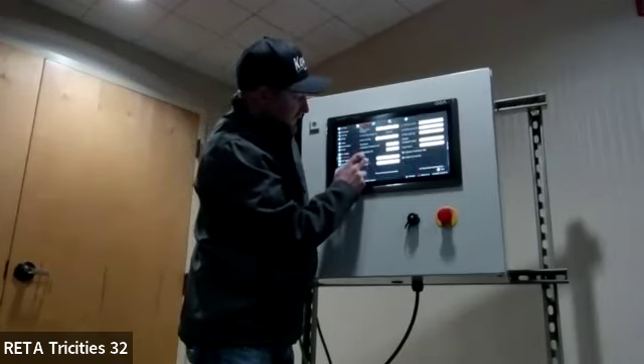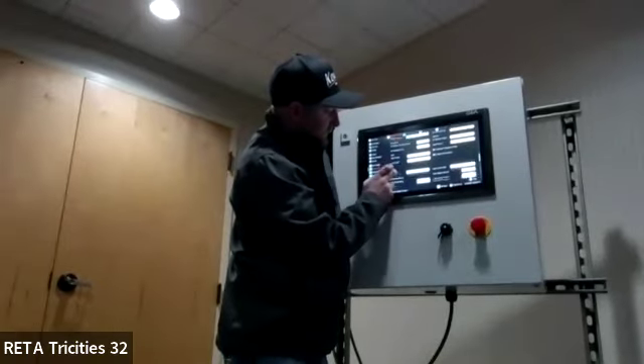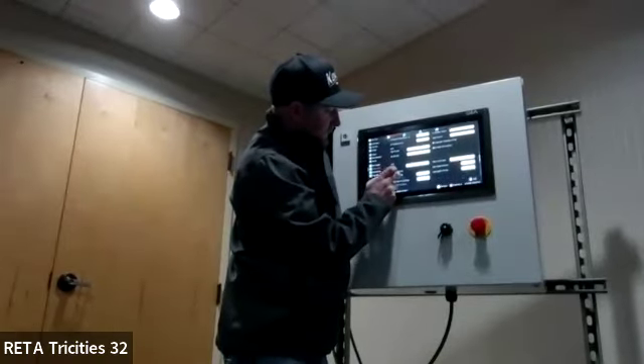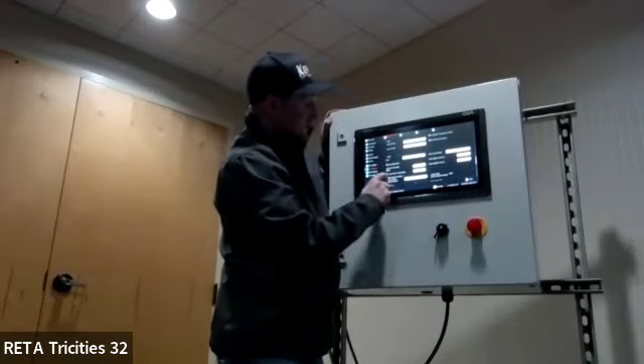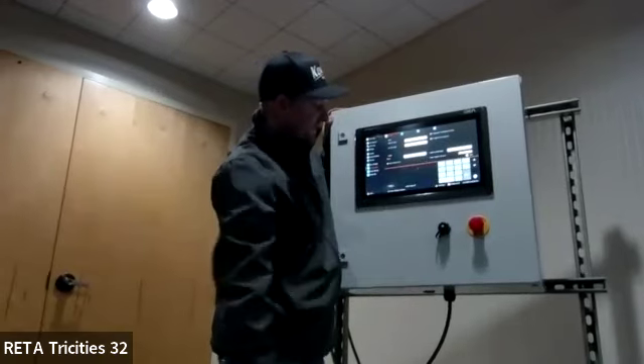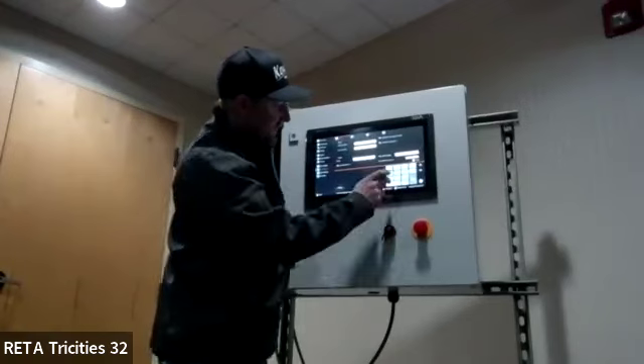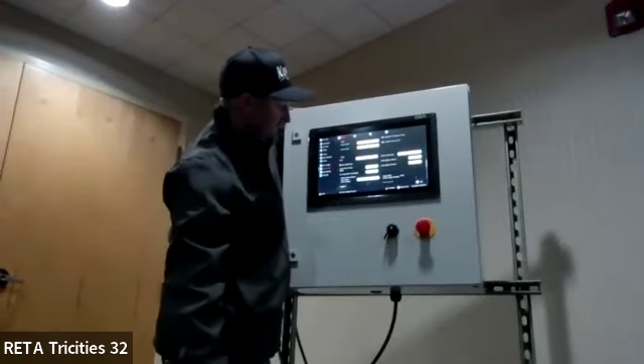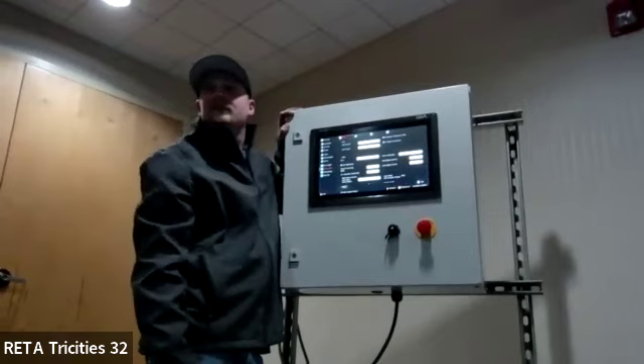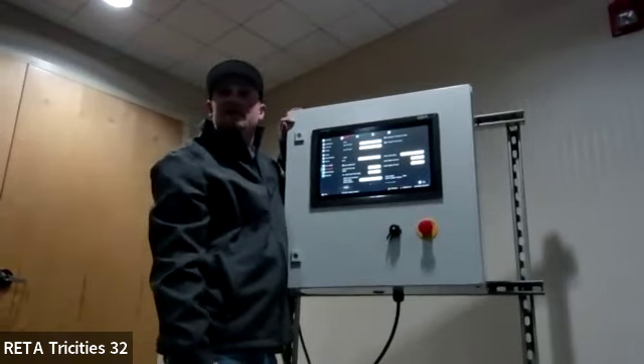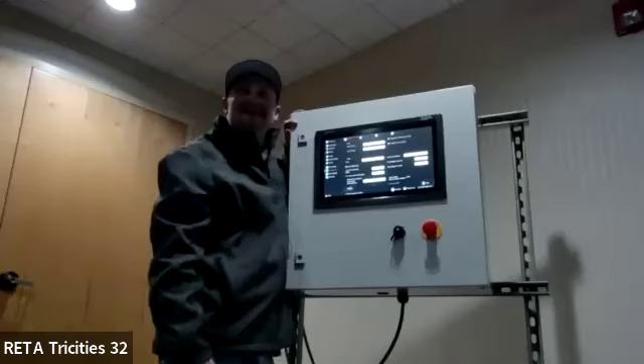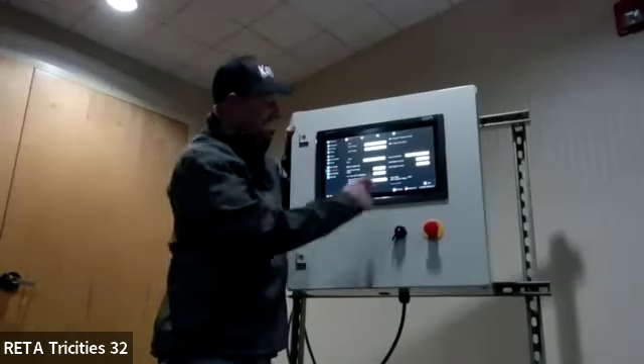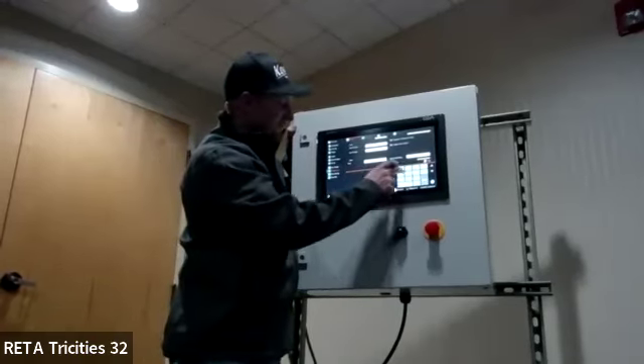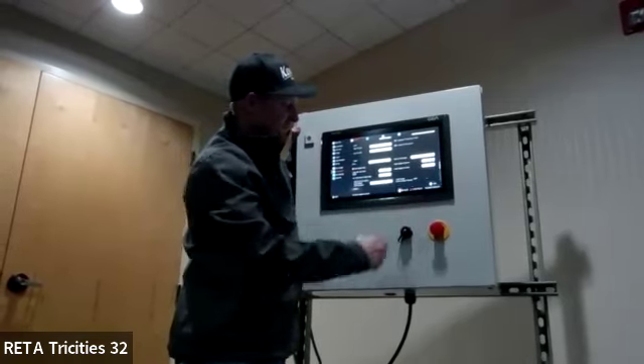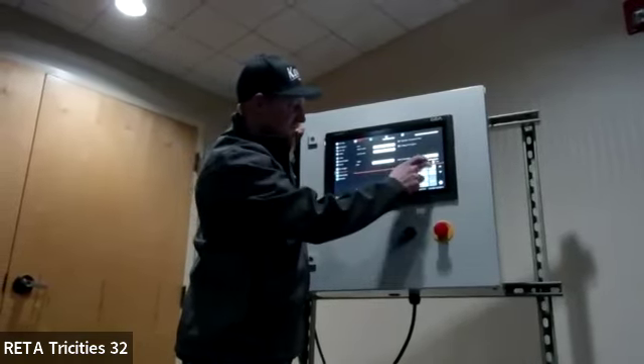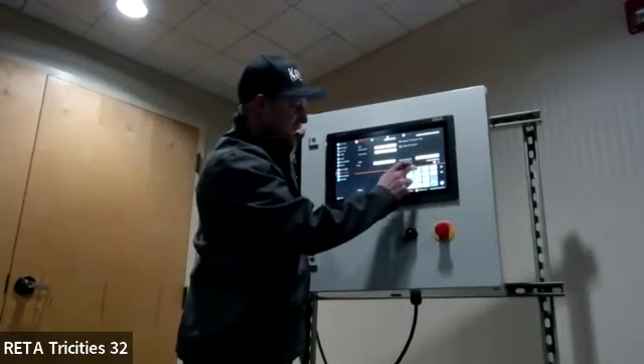I know sometimes it sucks to wait 9 minutes, but if you try to start a screw that's full of oil, you're going to know. So right there, minimum motor start to start delay. Let's see if I can set that at 0.1 minute. So if you have admin rights, you can blow up your motor. Let me put that back to 20 just in case somebody goes and puts this on and doesn't catch that. So on service, it's not accessible, it would have to be an admin. Yeah, you have to be an admin. Okay.